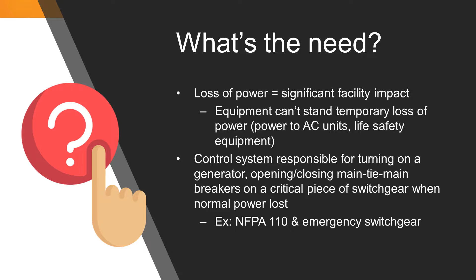Typically it's going to be wherever there might be significant impact to a facility, perhaps impacting life safety, or having significant repercussions in terms of production or efficiency. For example, in most hospitals there's a requirement that when there's a loss of normal power, a generator must supply power to the loads within 10 seconds. If you only have a single programmable logic controller responsible for ensuring that power delivery, the ability to provide power within that specified time frame would be jeopardized. So having a redundant controller would certainly be important in that type of application.